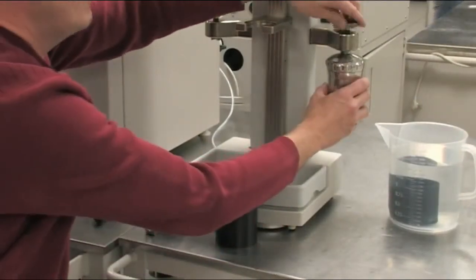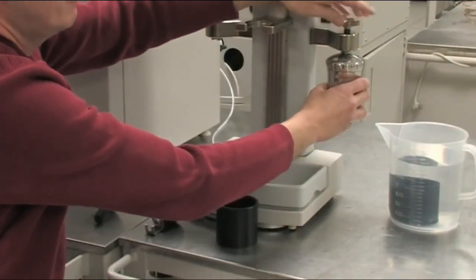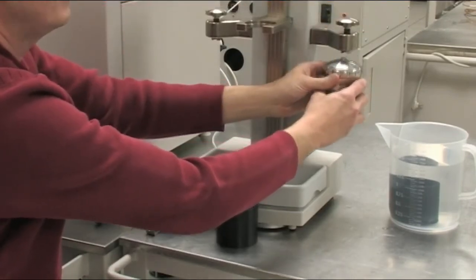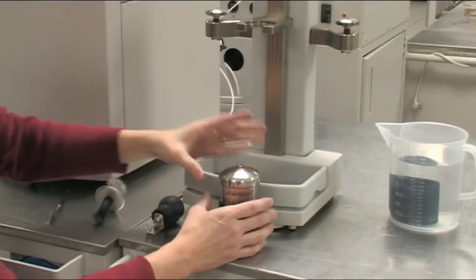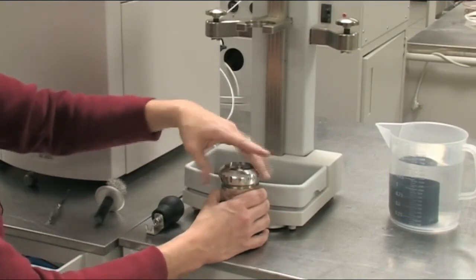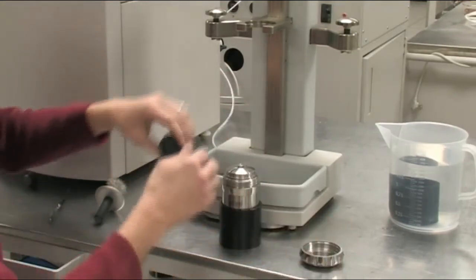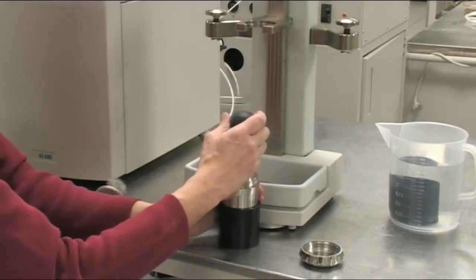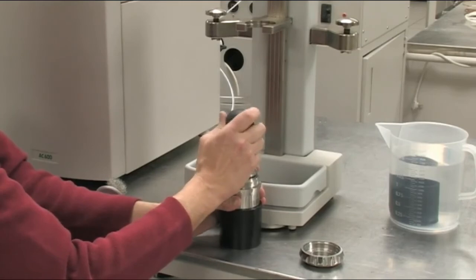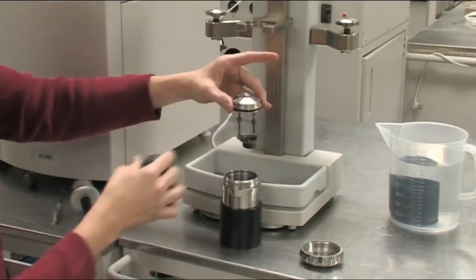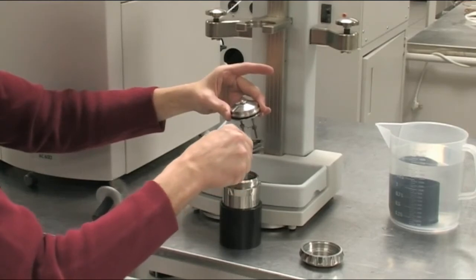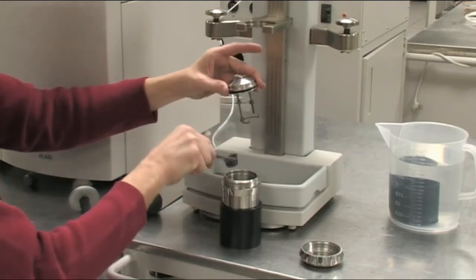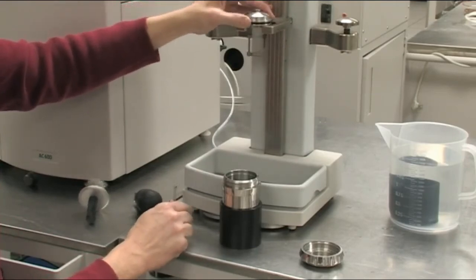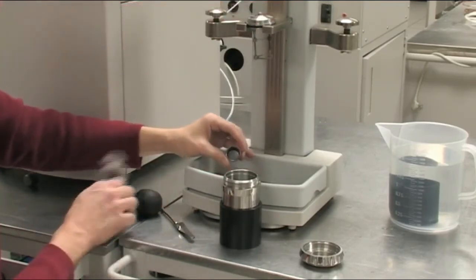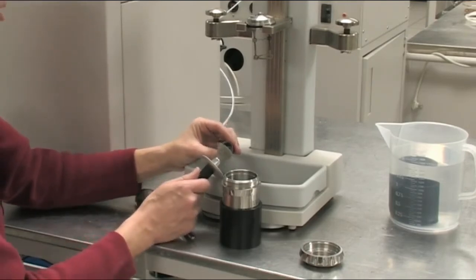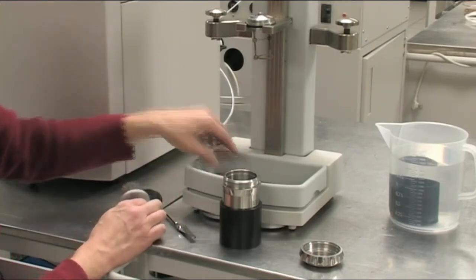After the vessel has been thoroughly vented, you want to unscrew the vent plug all the way. Then carefully slide the combustion vessel off. Loosen the seal ring. Use the igniter removal tool and carefully remove the igniter. Next, you want to take the crucible out and thoroughly clean it and rinse it. Clean it with a wire brush to make sure there's no debris left and rinse it thoroughly.